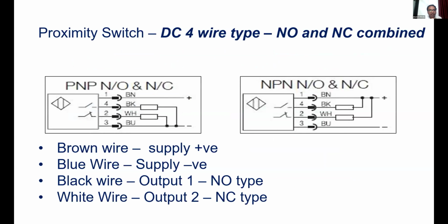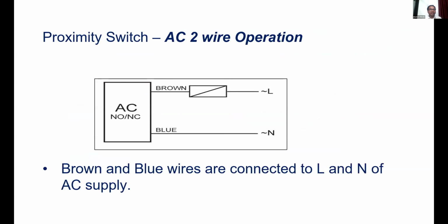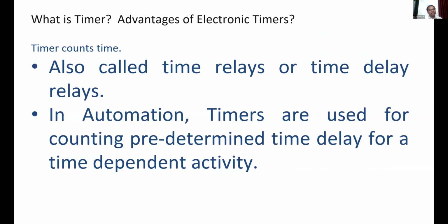There is the next one. It's a DC 4-wire. In DC 4-wire, the brown wire is positive, the blue wire will be the negative, and there will be two outputs, that is the black wire and the white wire. Again, AC 2-wire system.